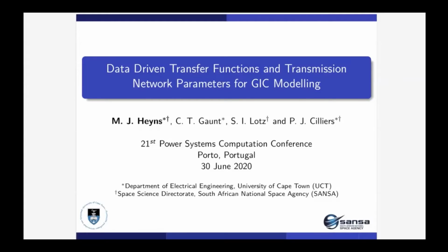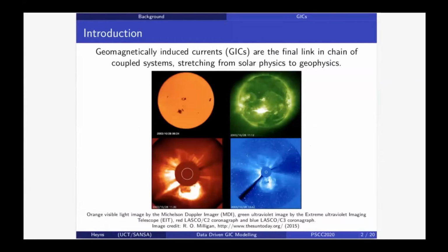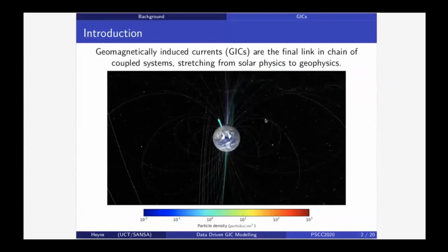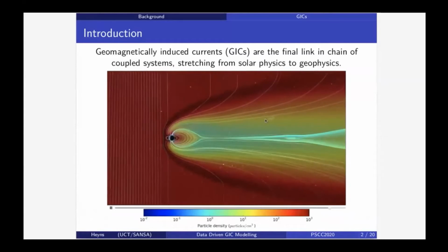And for those of you who are not familiar with the term, GIC in this case refers to geomagnetically induced currents. GICs are naturally occurring currents with their root in space weather and the sun. Over the 11-year solar cycle, large solar storms can occur, which eject huge amounts of plasma into the solar wind, which can in turn interact with Earth's magnetic field. This interaction causes large-scale fluctuations in the Earth's magnetic field, which through Faraday's law of induction can induce electric fields on the Earth's surface. Given a large grounded conducting network such as a power grid, these induced currents can cause real currents in the grid with detrimental effects to transformers.